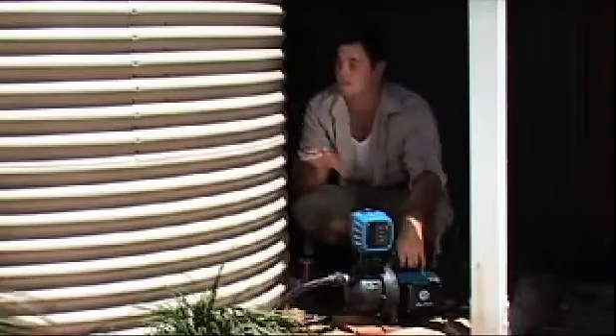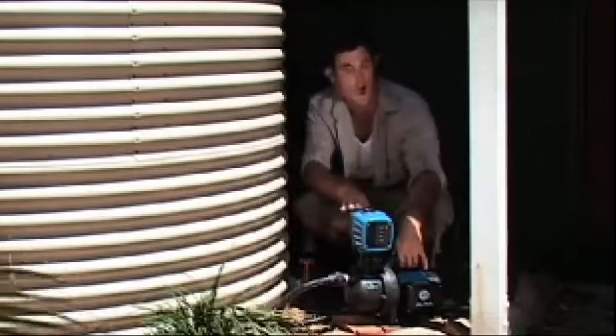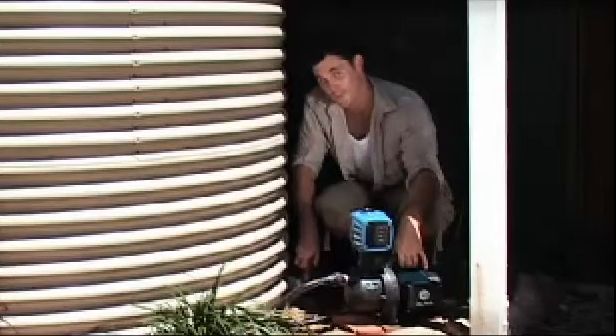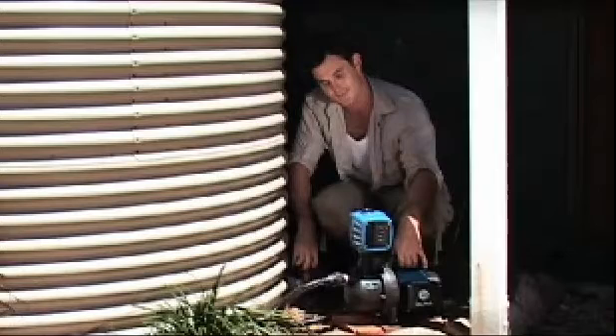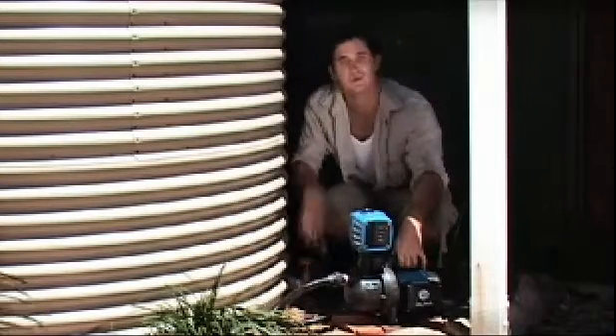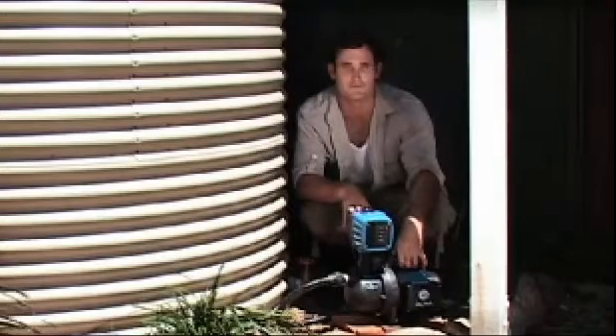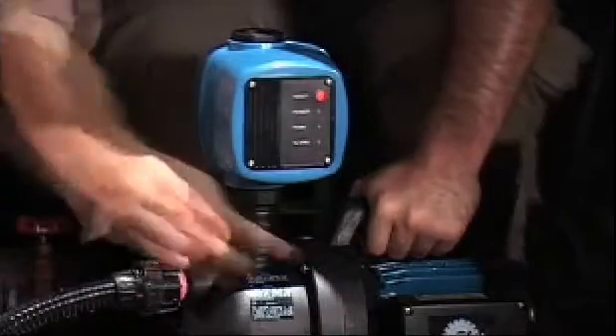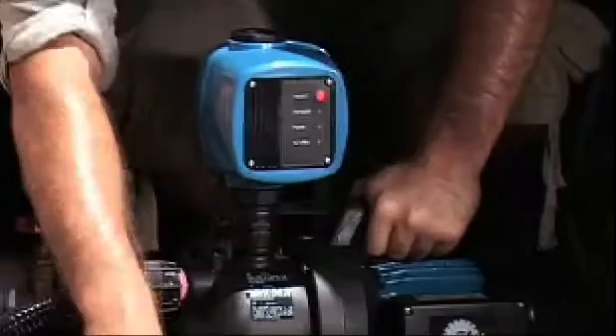The pump is now correctly attached to the rainwater tank. This is the best time to prime the pump. Firstly, make sure the water level in your tank is higher than your pump. Then open up your gate or ball valve and allow the water to flow through, then shut the valve back off. Your pump should now be filled with water. If your particular model of pump has a priming plug on the top, loosen the plug — this will release any air trapped in the pump body. When you see water flow, close the valve from the tank and replace the priming plug.